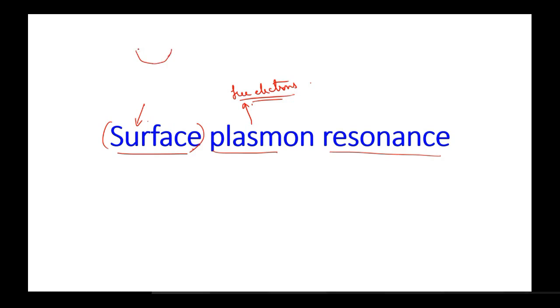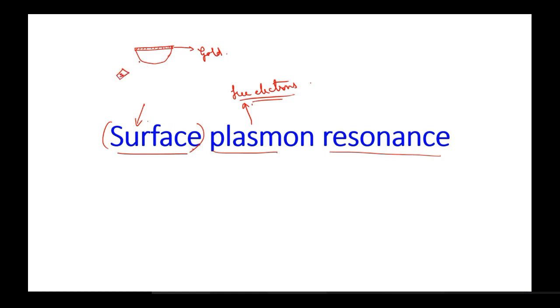In a typical surface plasmon resonance setup, you will find that there is a prism beneath, and then you have a layer of metal over it. In our case it is basically a thin layer of gold. There will be a source of light which will be made incident and will be able to impinge onto this gold layer, and on the other hand we'll have an array of detectors.